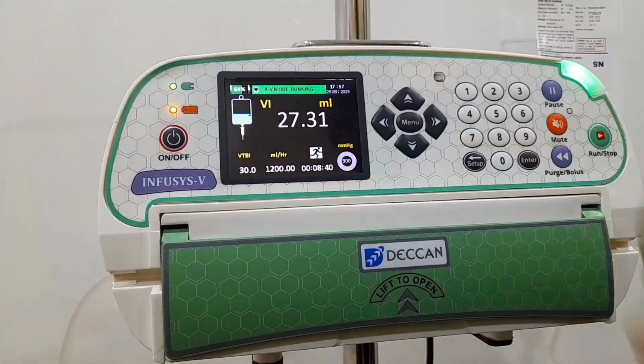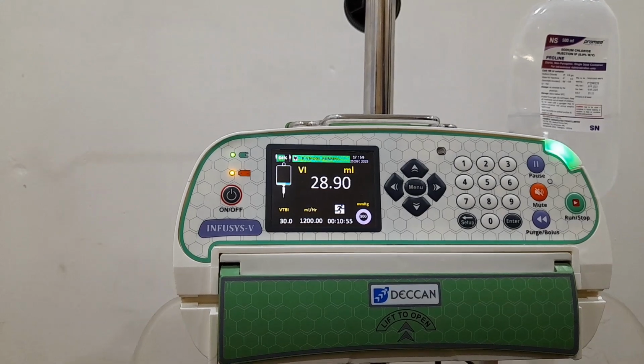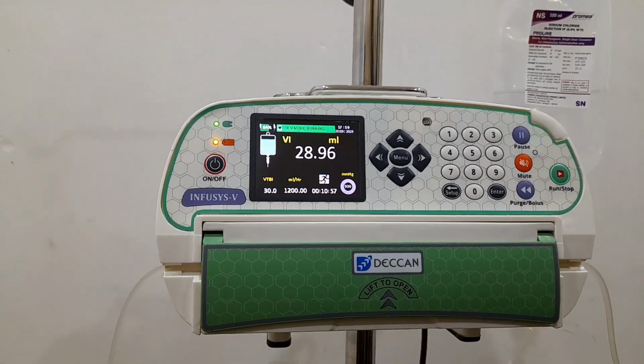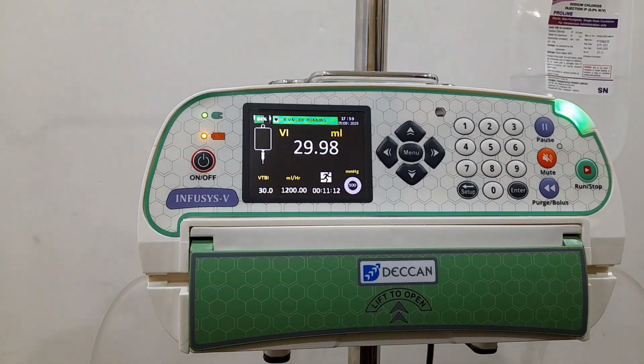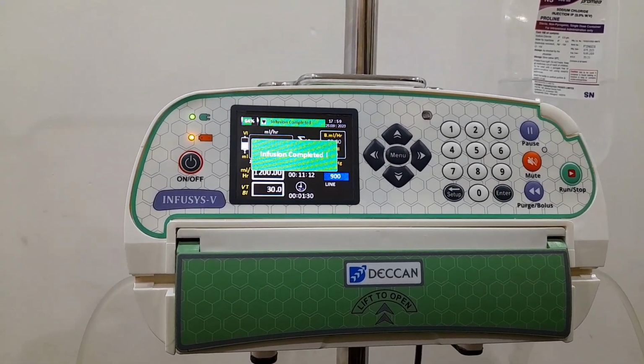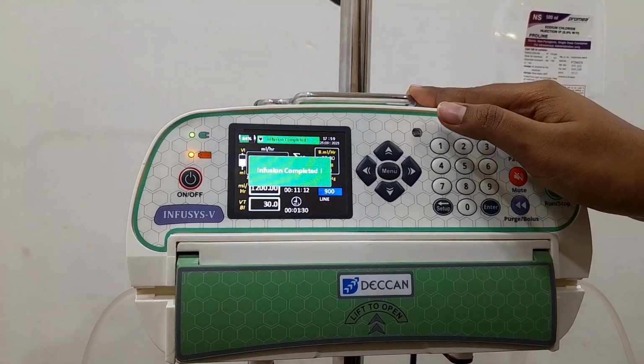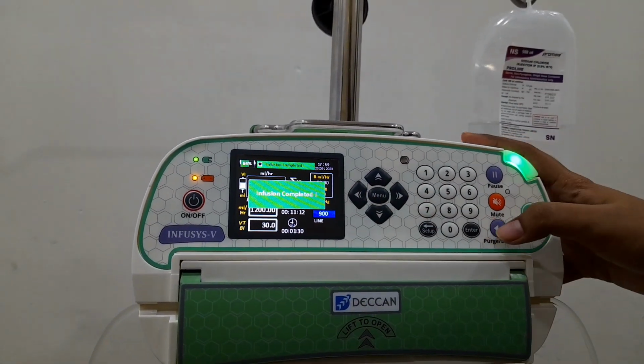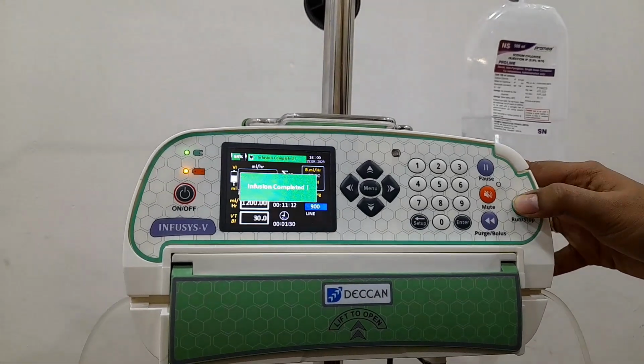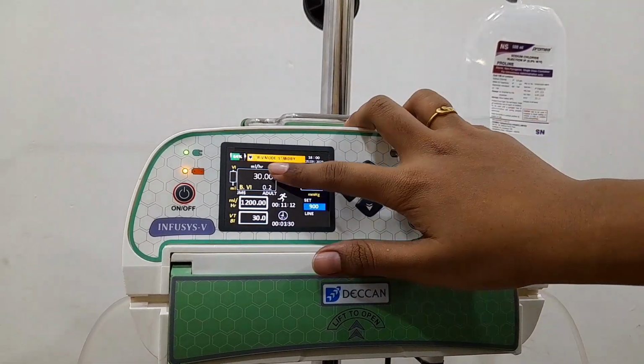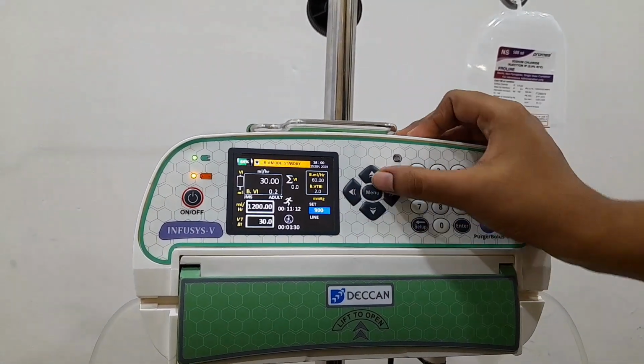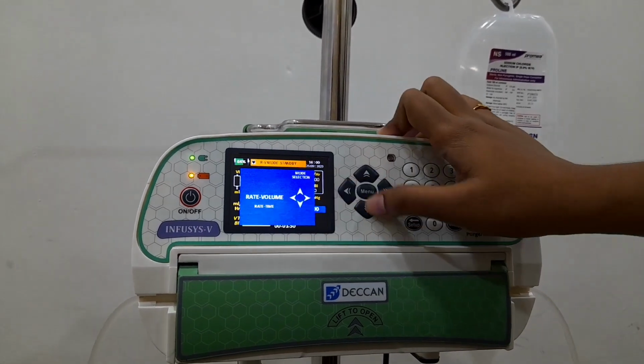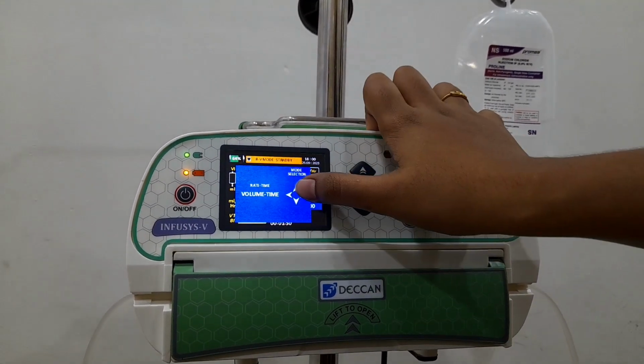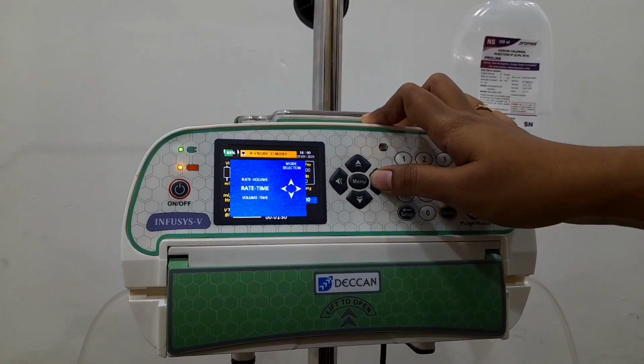It has almost reached the targeted volume. Once the target volume is reached, a pop-up displays infusion completed. Yes, the infusion complete pop-up occurs. Press the run or stop key to stop the infusion after completion. The running condition of the status bar changed to standby mode. Now press the menu key, press down navigation and right navigation to select RT mode.